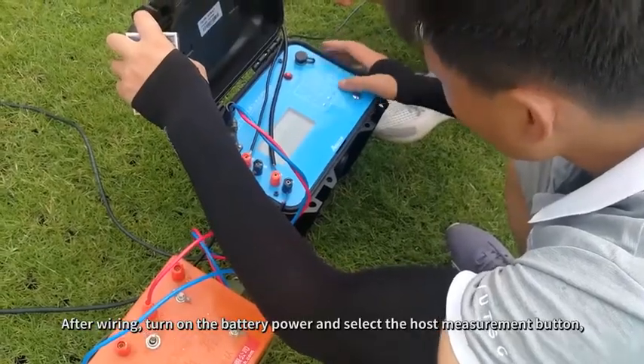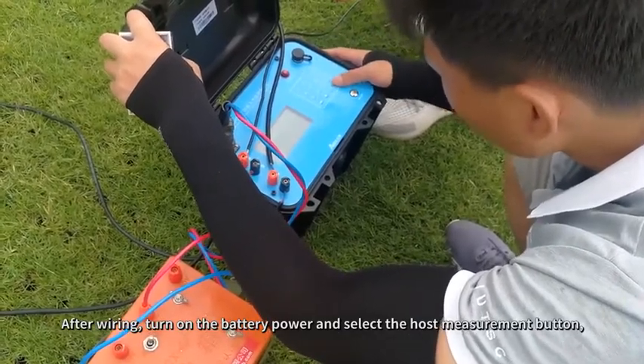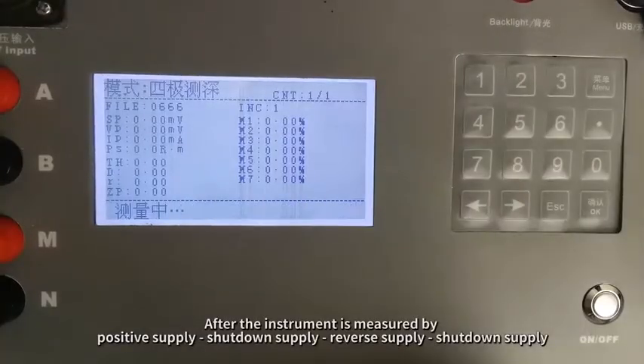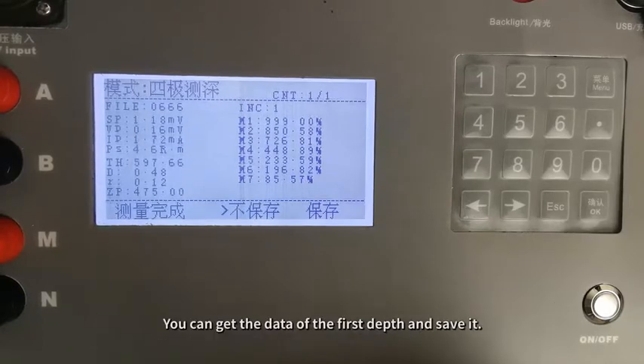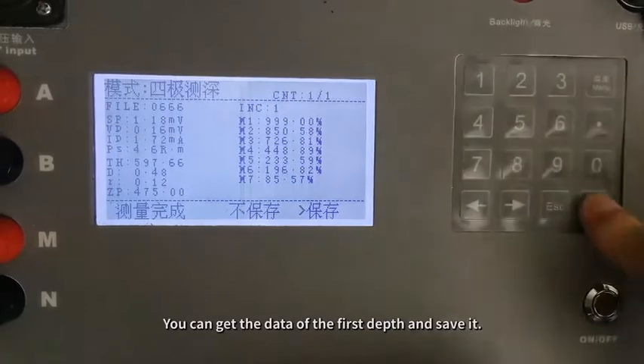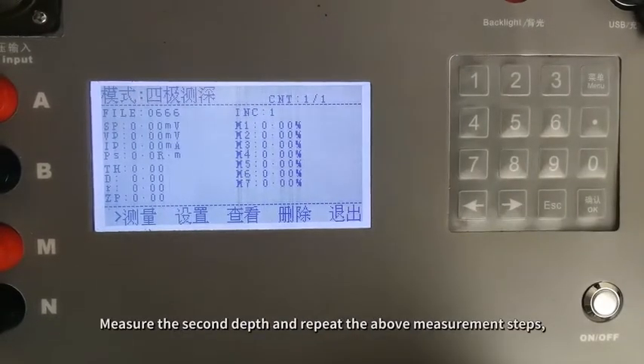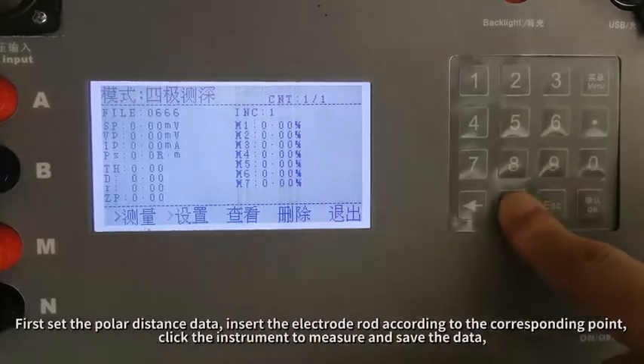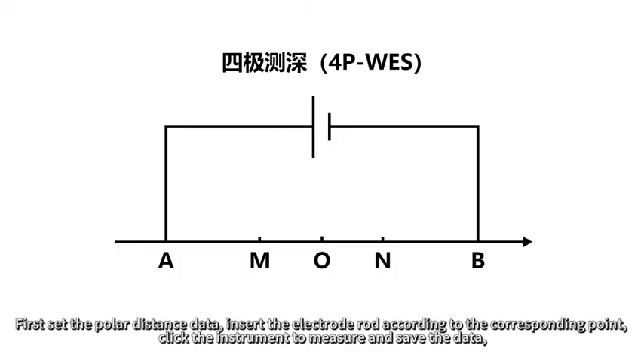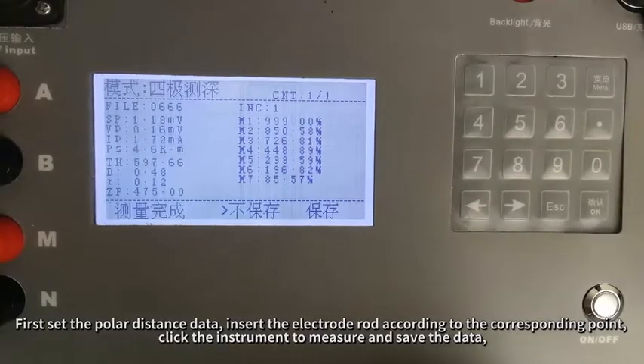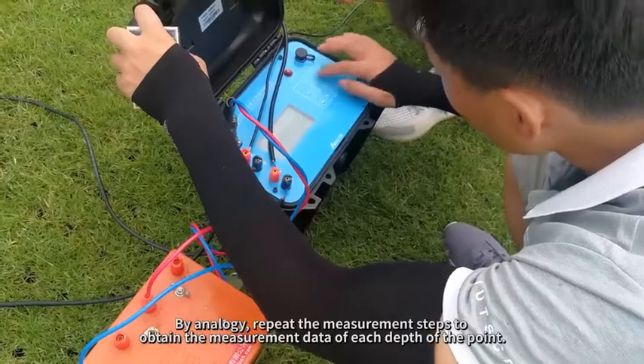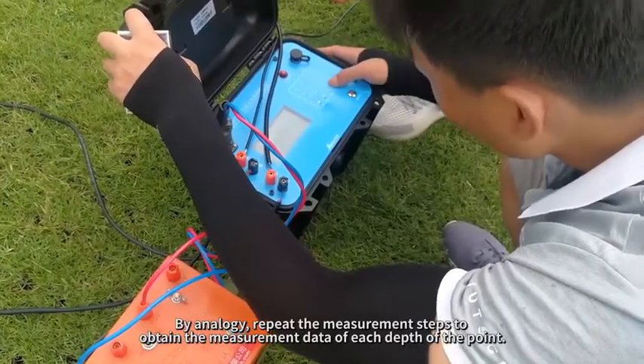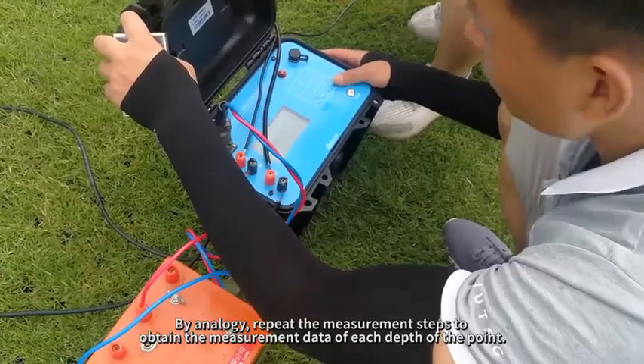After wiring, turn on the battery power and select the host measurement button. The instrument measures by positive supply, shut down supply, reverse supply, shut down supply. You can get the data of the first depth and save it. Measure the second depth and repeat the above measurement steps. First, set the polar distance data. Insert the electrode rod according to the corresponding point. Click the instrument to measure and save the data. By analogy, repeat the measurement steps to obtain the measurement data of each depth of the point.